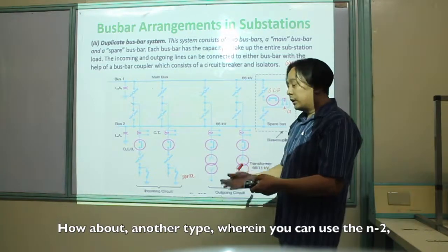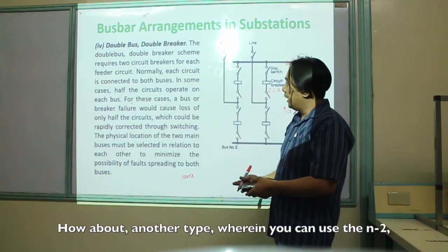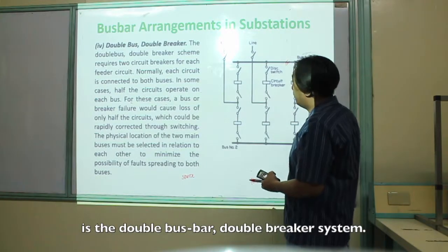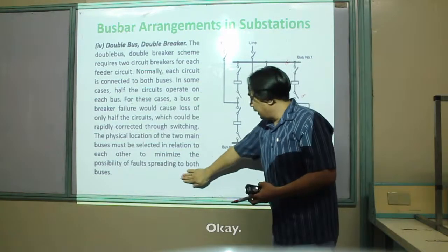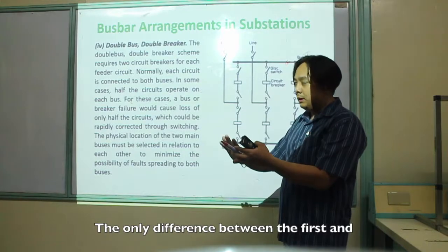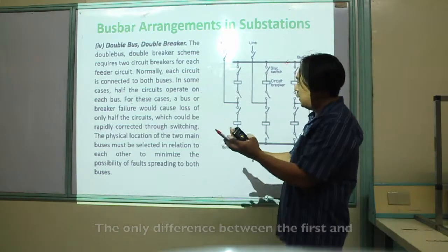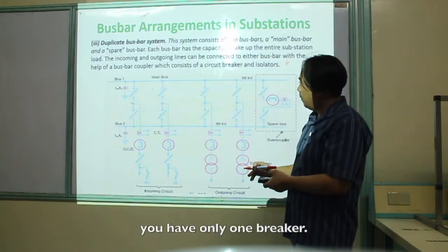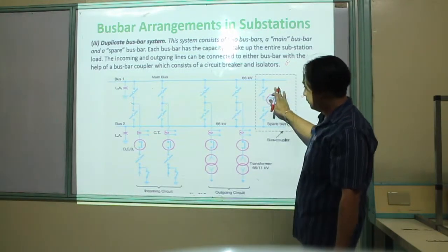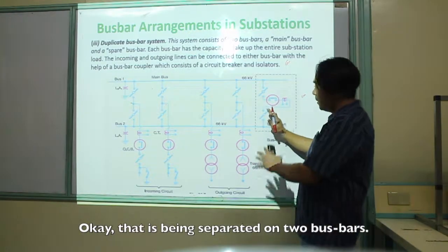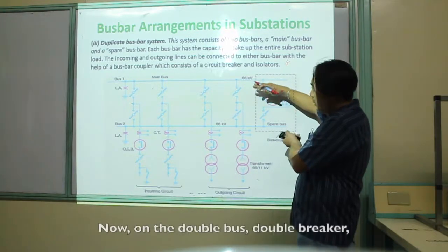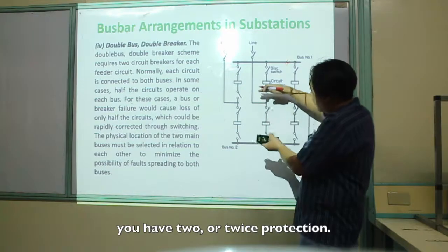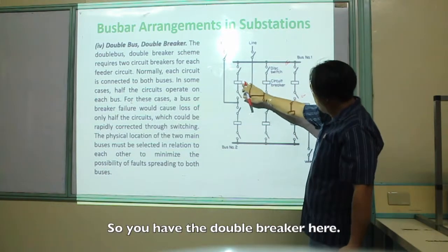Another type for N-2 contingency is the double bus and double breaker system. The difference between the duplicate bus bar and this type is that in the duplicate, you have only one breaker separated across two bus bars. In the double bus and double breaker, you have two or double protection — you have the double breaker here.